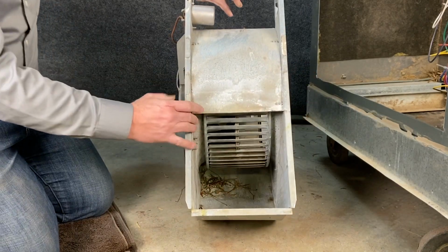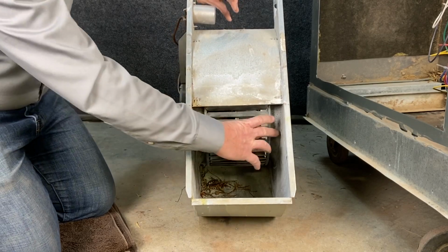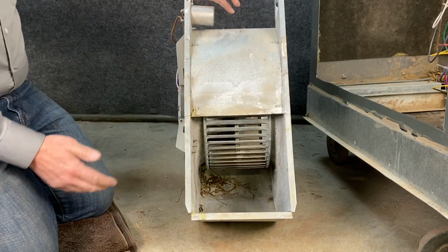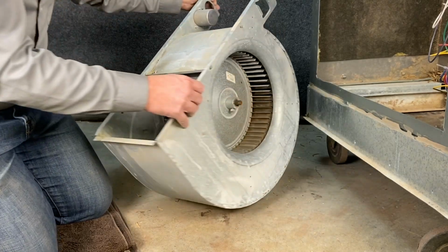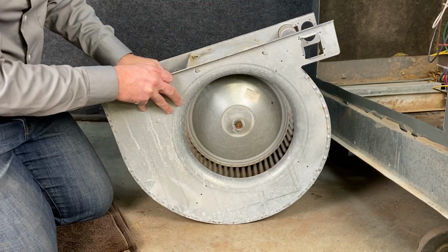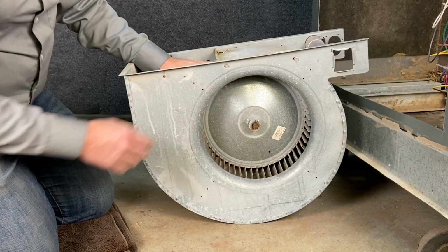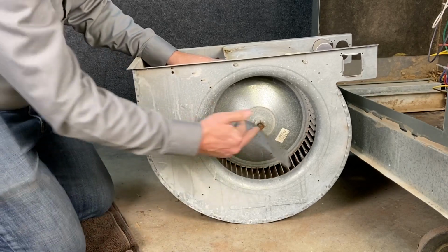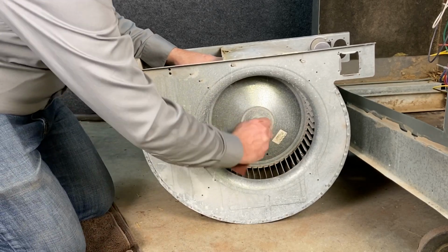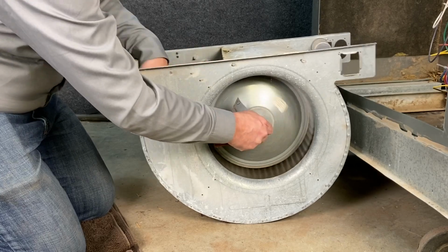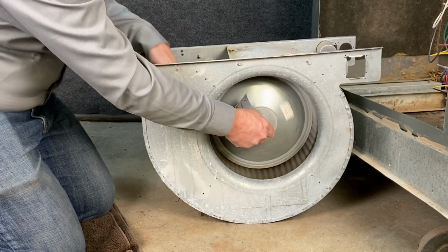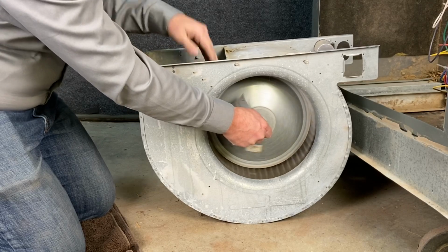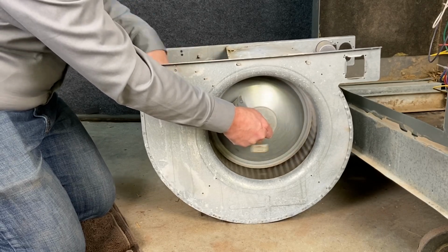This particular brand installs their blower housing with a very close tolerance, so it's usually not much of an issue with this particular brand. So if we're going to pull this blower, one of the things we need to do is separate this wheel. So what I'm going to do first is take my sand cloth and sand up this shaft to make sure it's nice and clean. And one little trick is you can hold the sand cloth on here, spin the wheel, and it helps sand it for you nice and quickly.